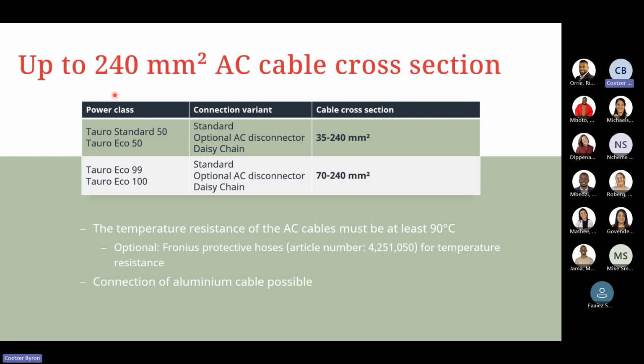Again, on the cable sizes, with the Tauro standard 50, the 50 kilowatt variant, this is both for the standard and optional AC disconnector as well as daisy chain options. You can have AC cable coming in of either 35 to 240 mil squared. But if we are using the larger variant units, like for example the Tauro Eco 99 and Eco 100, we are then limited on the AC side from 70 mil all the way up to 240 mil squared coming in on the unit. We also state that the temperature resistance of the AC cables must be at least up to 90 degrees centigrade.